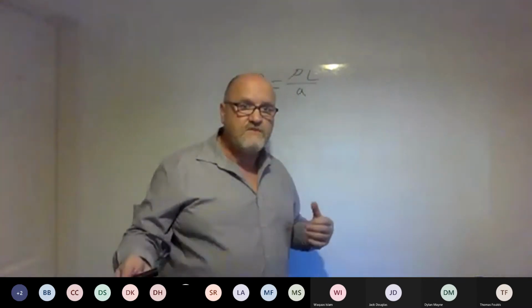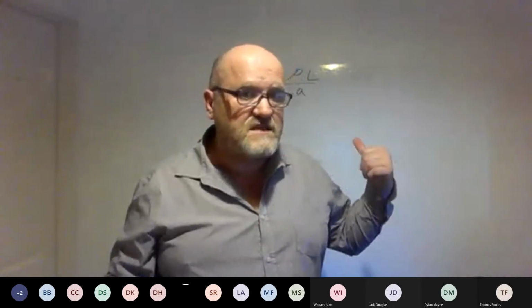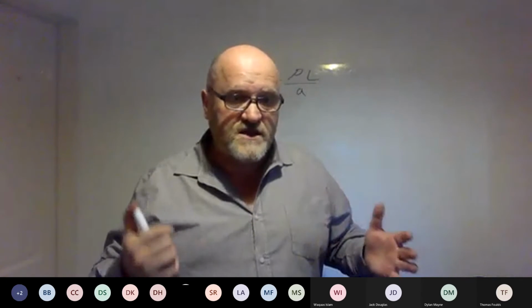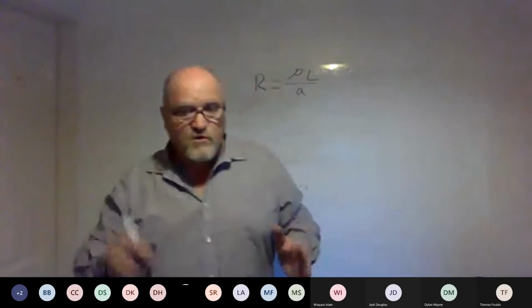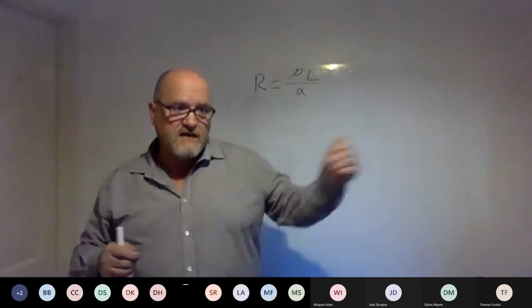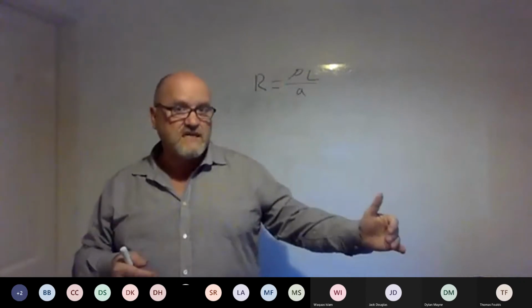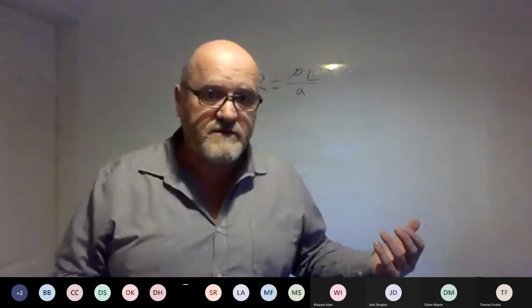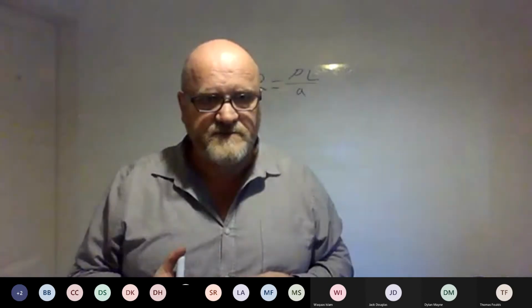And if you're testing their work, and their readings are not what you've worked out, it can take you a couple of minutes to do this, and you will do it on site, trust me on that one. When you're working with drawings on site and you know your cable runs, you will work them out before you install them, or if you're testing them, you'll work out what you should be getting when you go and test it. And if it's not what you expected to get, then you know there's a problem with the job. Does that make sense?